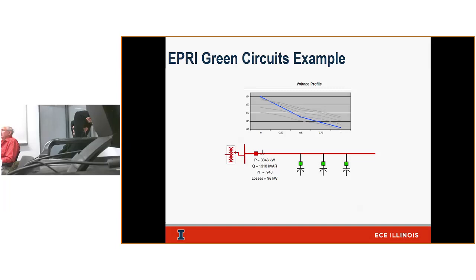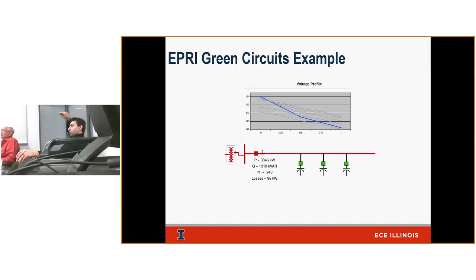What we're targeting here is efficiency at the feeder head: minimize losses, fix power factor to get as close to unity as possible, and flatten the voltage profile so I can reduce it as much as possible. Right now I can't reduce this voltage profile — if I ask the LTC to reduce voltage, I'm going to go into a violation at the last node. So I'll utilize these cap banks to flatten the voltage profile, improve power factor and losses, then reduce the voltage to achieve energy savings.